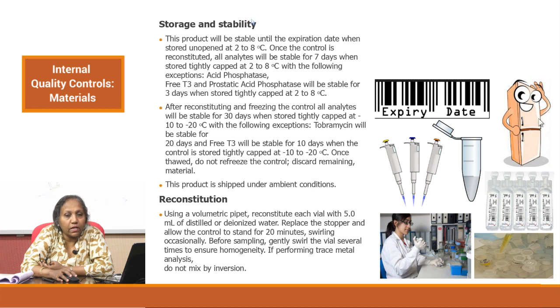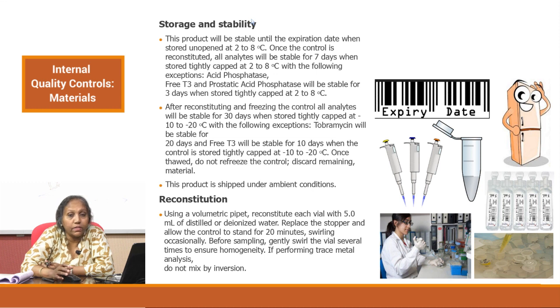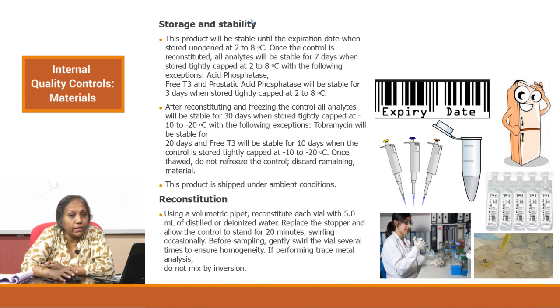Look at the expiry date, understand the conditions of storage, ensure your pipette is calibrated, and have the aliquot tubes ready. The volume inside the aliquot tube must be thought through while storing. Use only the prescribed kind of water — injection water is the best for reconstitution. Training of your technician is extremely important in how to reconstitute quality control material. This is important whether it is an internal control or external control. Every caution should be taken and the operator should be thoroughly trained.